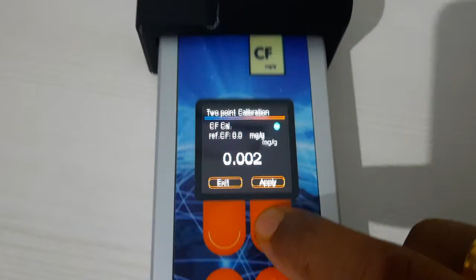Once it is 0, you press apply. So now coming to the second application, the second point. Once it is 0, you can press 0. Sometimes it will give a correct calibration, and sometimes it will not. So now we can exit and try to measure it again. Once we are measuring, it is showing minus 0.0002. This much error is okay to get the results. Normally you need to calibrate up to 2 digits.